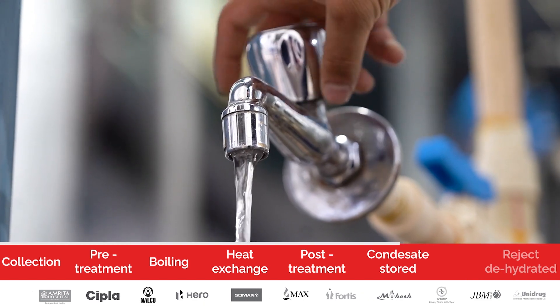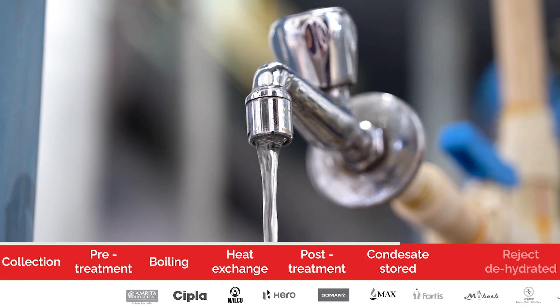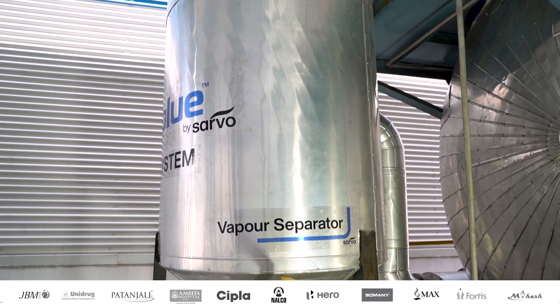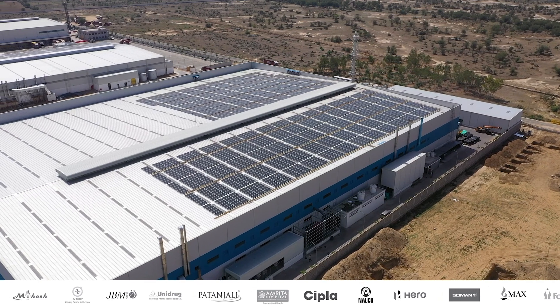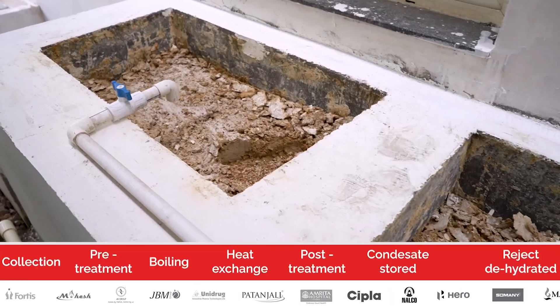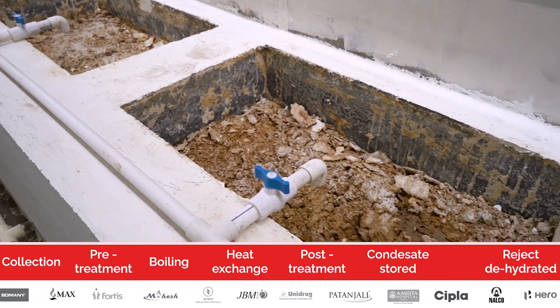The condensate generated after giving heat to the incoming feed is collected in the condensate tank. This condensate water can be recycled back to a desired process. On the other side, the reject is taken out from the evaporator system and transferred to a centrifuge to remove suspended solids. The collected suspended solids have a moisture content of around 30% weight by weight, and the dewatered sludge is further dried under sun.